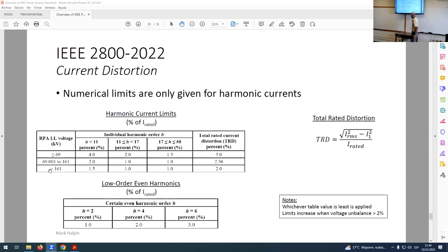This point down here in this box is potentially problematic. One of the things that we had to include in 2800, from the utility perspective, we had to accept from the inverter manufacturers this little box, the implications of this. When the interconnection is into the power system where there's significant unbalance, then the current limits have to be allowed to increase. The inverter manufacturers insisted on this.